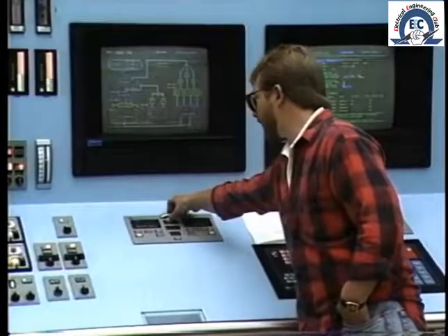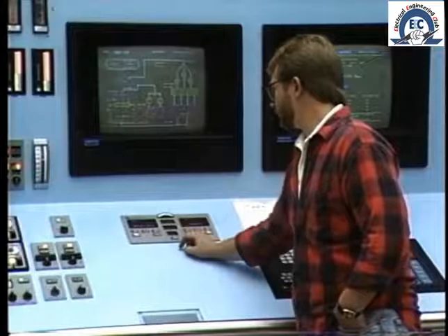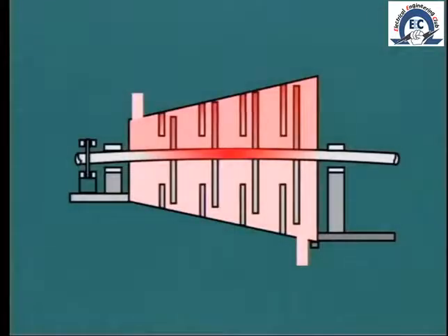The operator must take care not to increase steam flow or steam temperature too rapidly, as this could lead to unequal expansion of components and possible distortion. When this occurs on the rotor, it leads to an increase in eccentricity. The shaft and rotor take on a slight bow due to temperature distortion, and this is exaggerated by the centrifugal force of rotation.